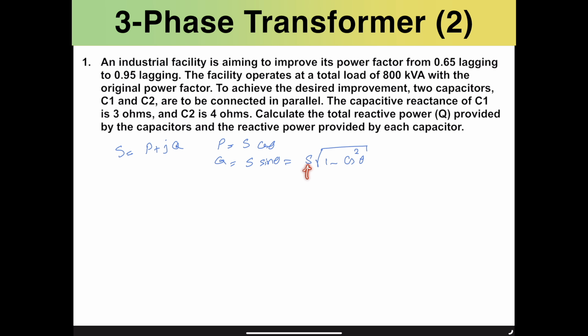Now we have S, the initial apparent power, and we know the initial power factor is 0.65. We can find the initial Q, the reactive power. Then we use the same approach to find the desired reactive power with respect to the ideal, desired power factor. The subtraction of these two gives the added reactive power needed in the system.